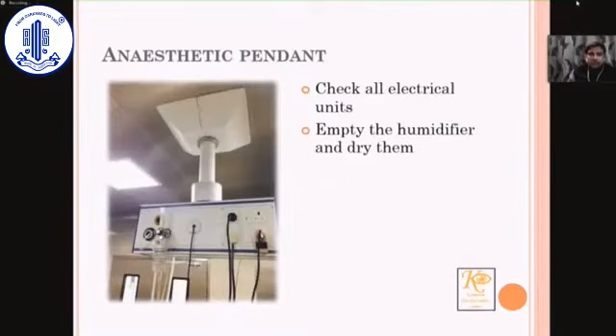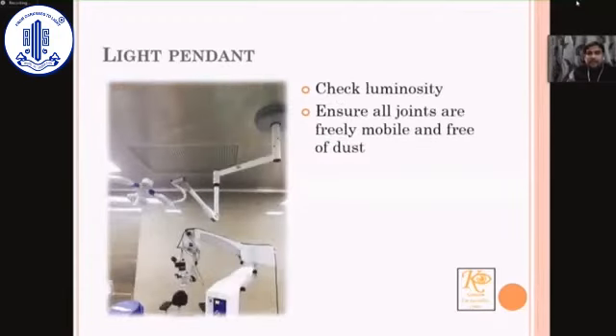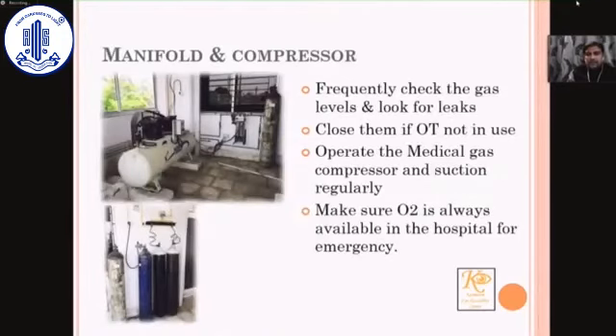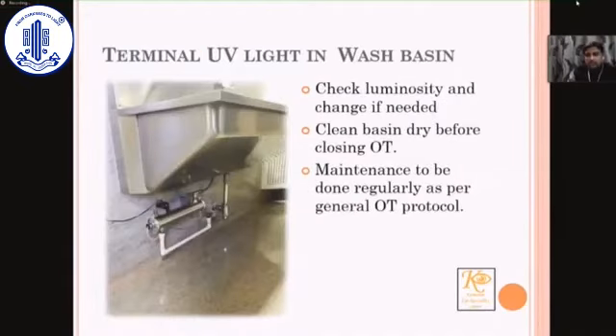The anesthetic pendant: the most important thing, I would say, is to empty the humidifier and keep it dry and make sure all the electrical connections are disconnected. The light pendant, if you have one, make sure you check the luminosity of the light and ensure it is free of dust and all the joints are freely mobile. The anesthetic manifold should be checked on a daily basis to ensure that the oxygen levels are properly maintained. The wear and tear instruments should be checked on a daily basis. The terminal UV light in your wash basin also has to be checked. Clean the wash basins regularly with soap and water, preferably daily.